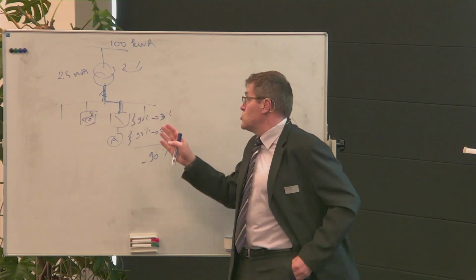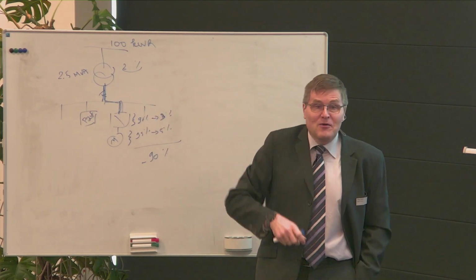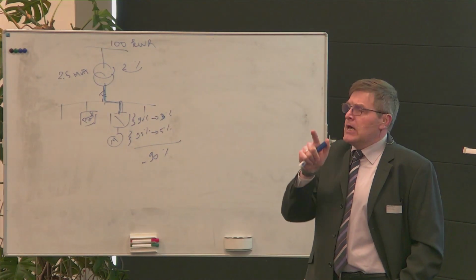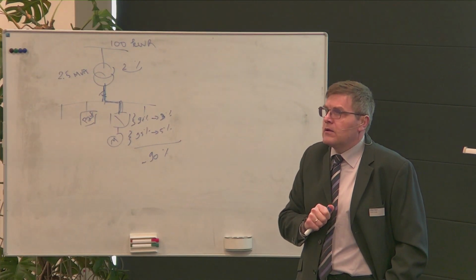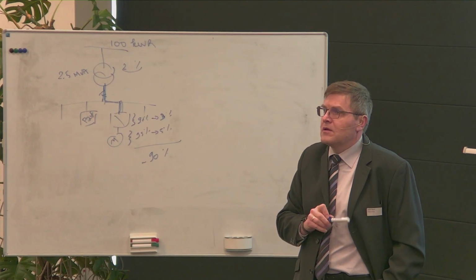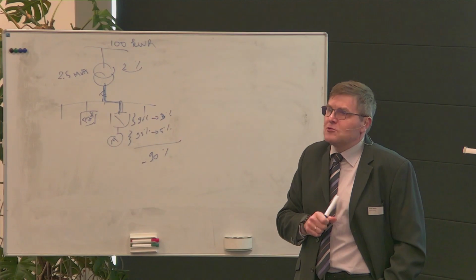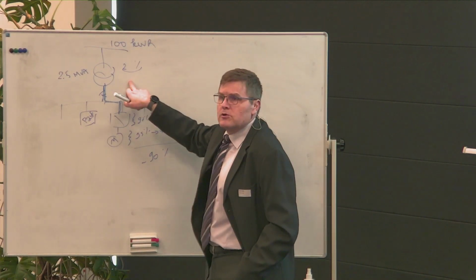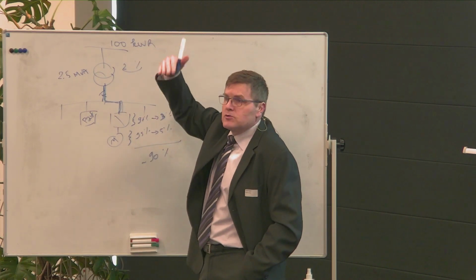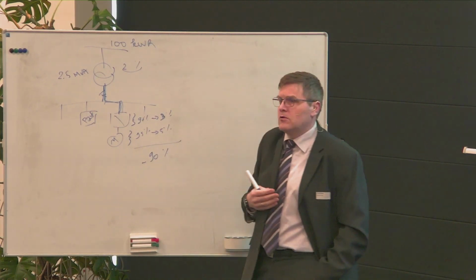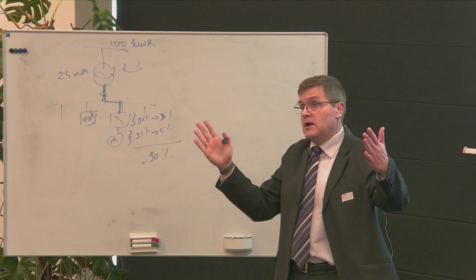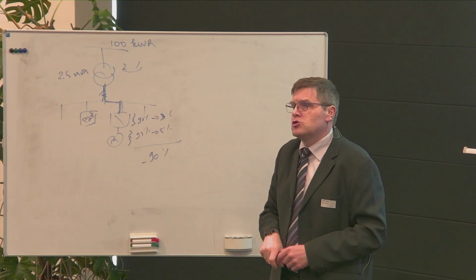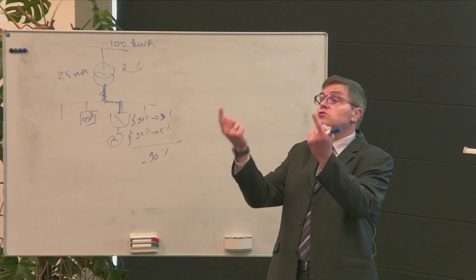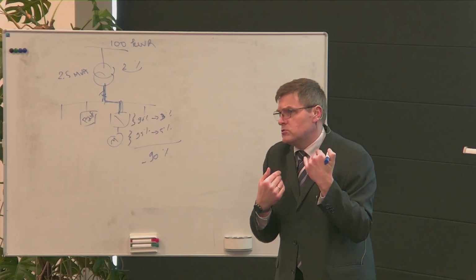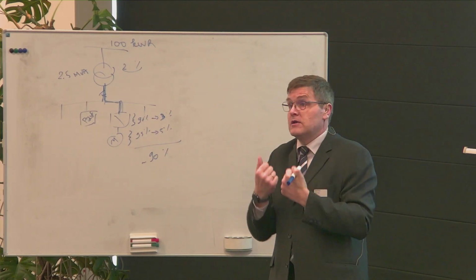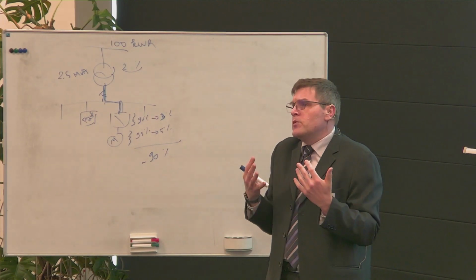And so the customer installed, I would say, 10 filters. But here, it's not for energy savings, unless you consume 7 hours of energy instead of 8. Indeed. The transformer was used at 80%, and now we use it at 100% or 97%. That was okay for the network, but the production time was reduced. So the impact here was reduced production time. An active filter will reduce the harmonic current, so we reduce the current in the line because you remove the current. So there are some savings in the transformer and in the line, but globally you have extra losses.